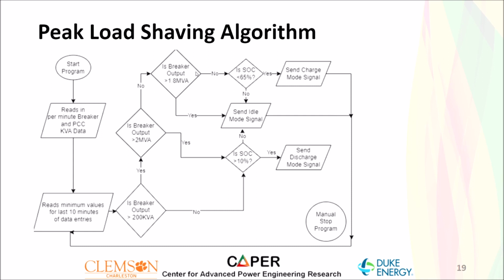But if it's not greater than 1.8 MVA, then we know that we're below that, and then we just see if the state of charge is less than 65%. And if it is, then we charge the battery till it gets to the 65% threshold that we've come up with. And once it gets there, we send an idle mode signal to keep it running like normal. And basically, once this is done, it will just keep reading in the last 10 data entries and go through that entire cycle again.